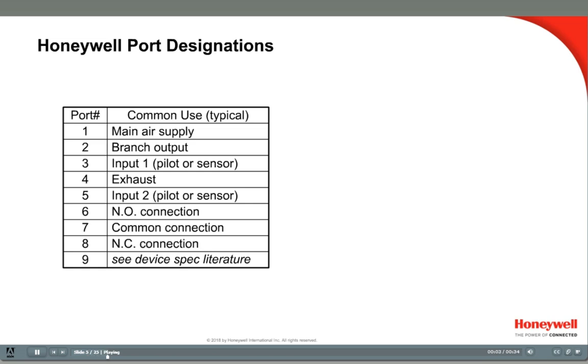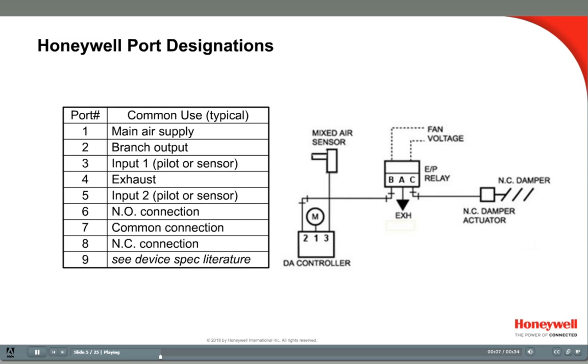The ports on pneumatic devices are labeled following this convention. The main air is always labeled with a 1 and the branch line is labeled with a 2. Ports labeled 3 and 5 are either inputs or pilot signal outputs. Here you can see how port 3 signals the damper actuator to fully open a damper when the fan is running. Other nomenclature commonly seen is M for main air and B for branch line air. These designations appear on the drawings in the following slides and in the installation instructions.